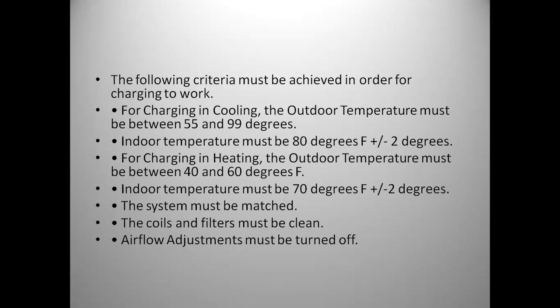So some following criteria must be achieved in order to charge the units. For charging in cooling, the outdoor temperature must be between 55 and 99 degrees. Indoor temperature must be, they say, 80 degrees, plus or minus 2 degrees. That's a pretty heavy load. So if you're much lower than that, everything on your chart will be lower. If you're at 85, 89 degrees indoors, obviously your chart wouldn't correlate exactly. All your pressures would be much higher.